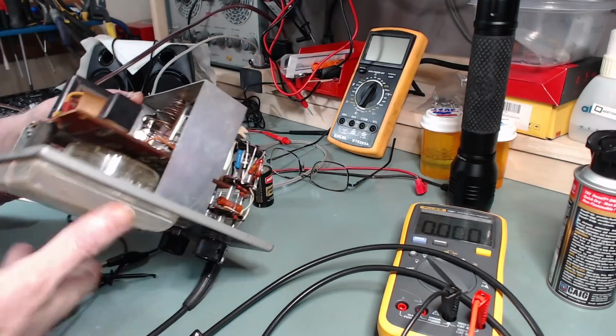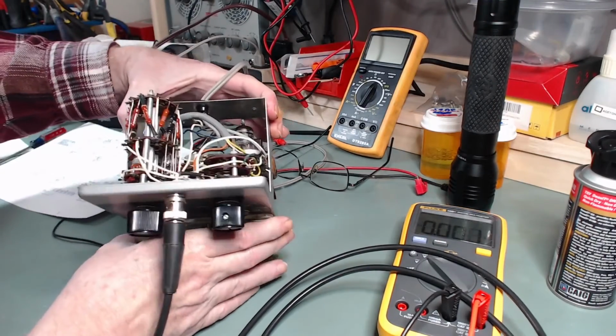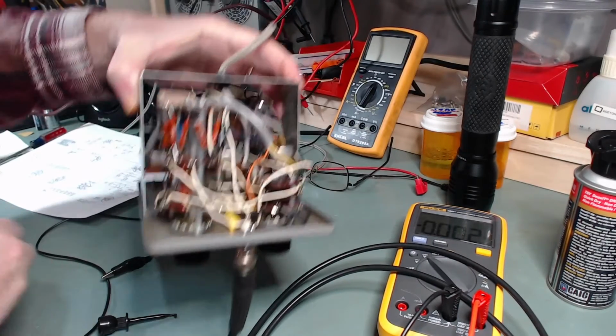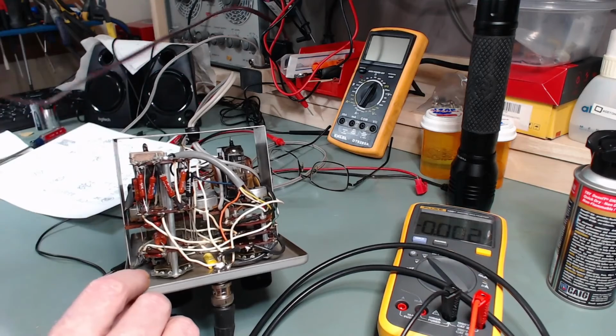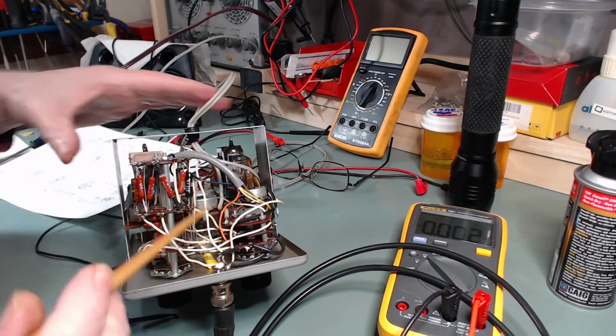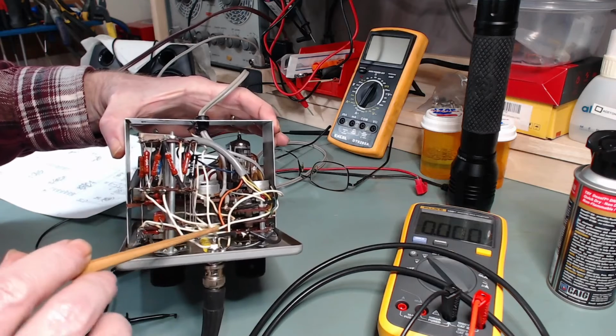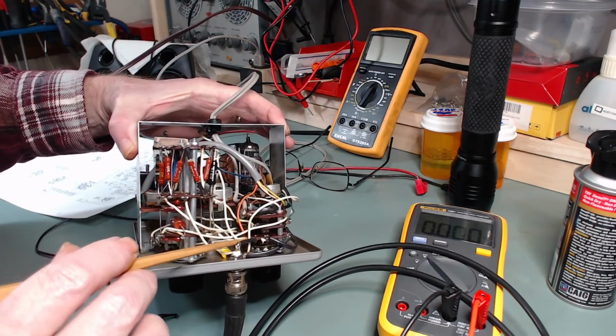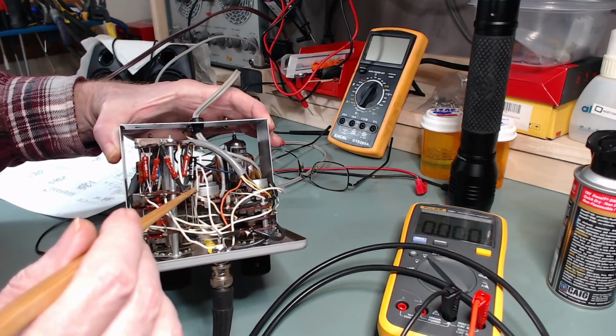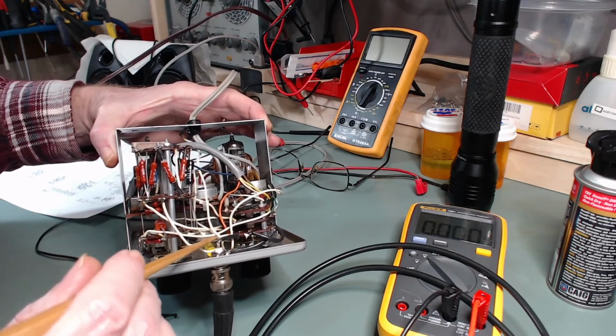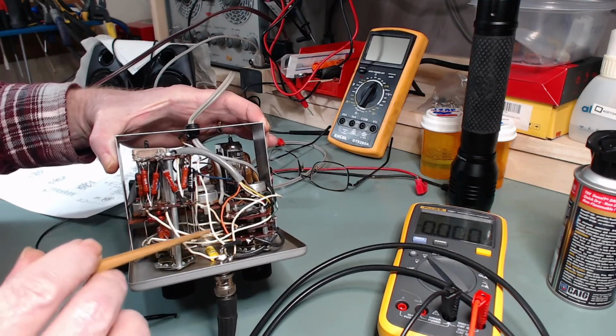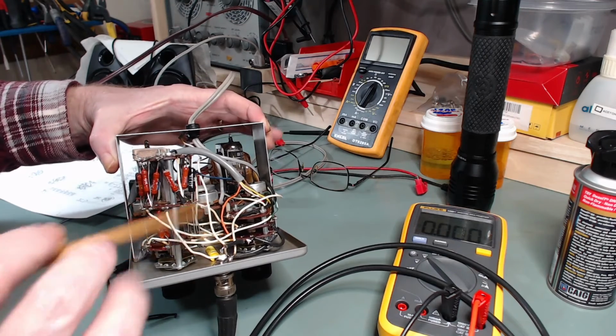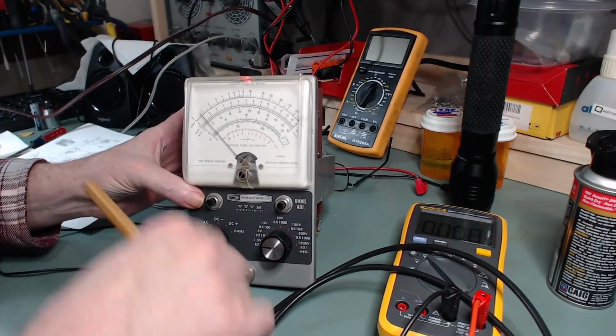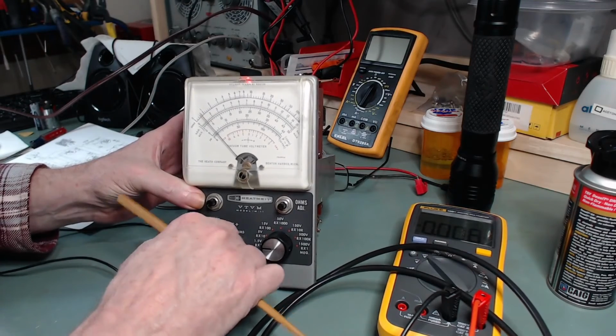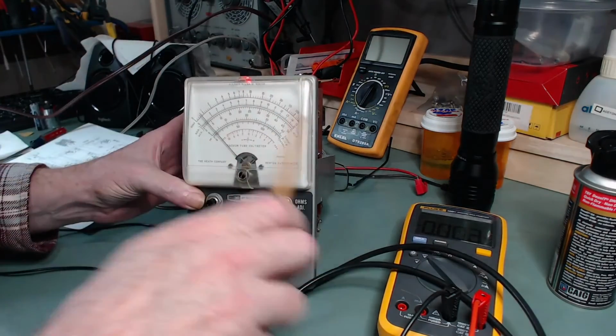I've done a little bit of tinkering. I believe, where is my non-conductive pointer? Right here. I've done some measurements, and this wire right here that goes from here to here, which taps into the 7 megohm resistor here, I believe that is a potential to replace this wire and put the 1 megohm resistor in there. That way, I can use just a straight through probe all the time. If I do use DC plus or minus, the 1 meg will always be in line.